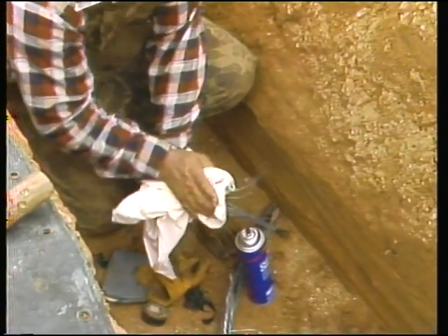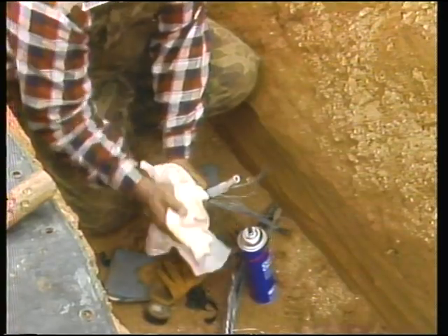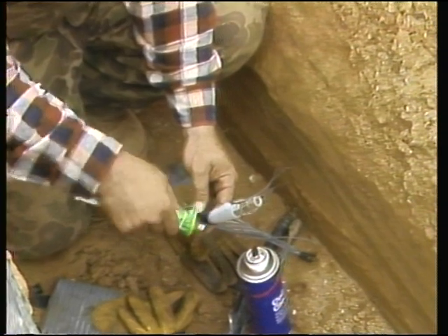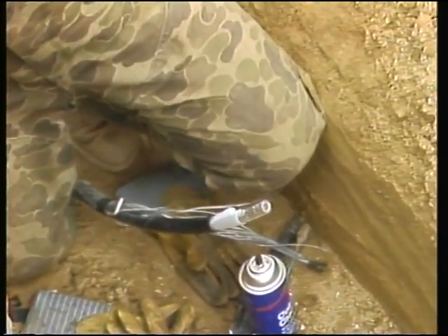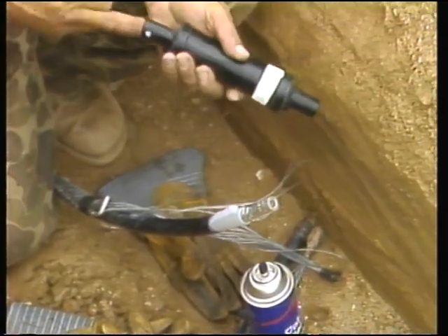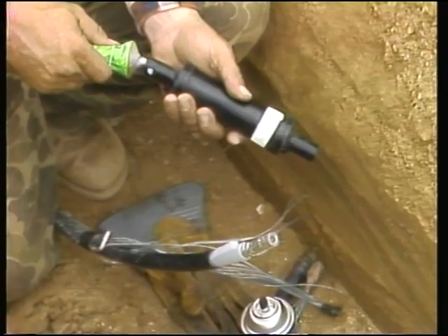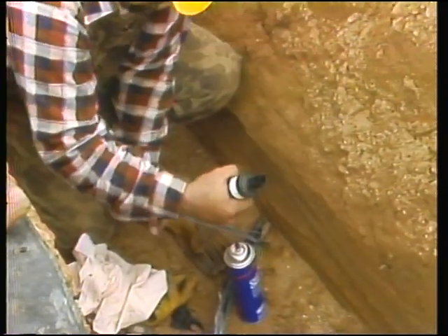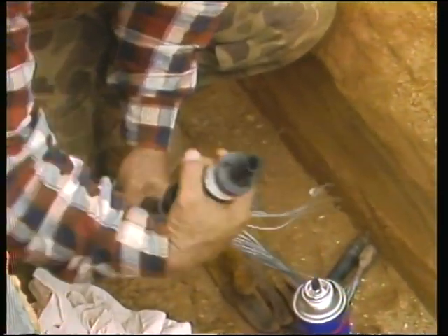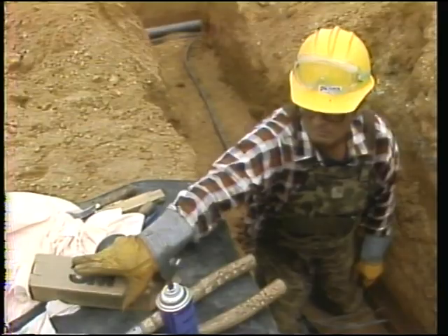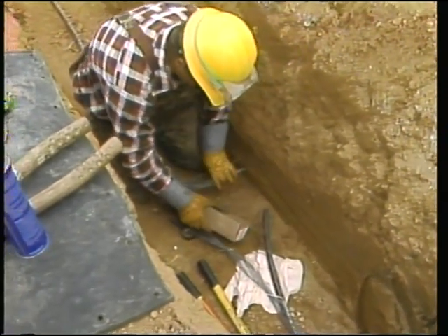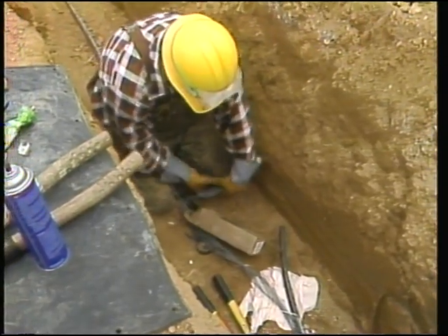Some insulation types may require that a non-conductive sandpaper be used. Then a small amount of silicone grease, which may also be supplied with the kit, is applied to the cable's insulation and to the semiconductive layer. The grease provides lubrication to ease the installation of the splice body. The workman then slides the splice body over the end of the cable. To keep the splice area clean while he prepares the other cable, the workman places the splice kit box over the splice body in the ditch.